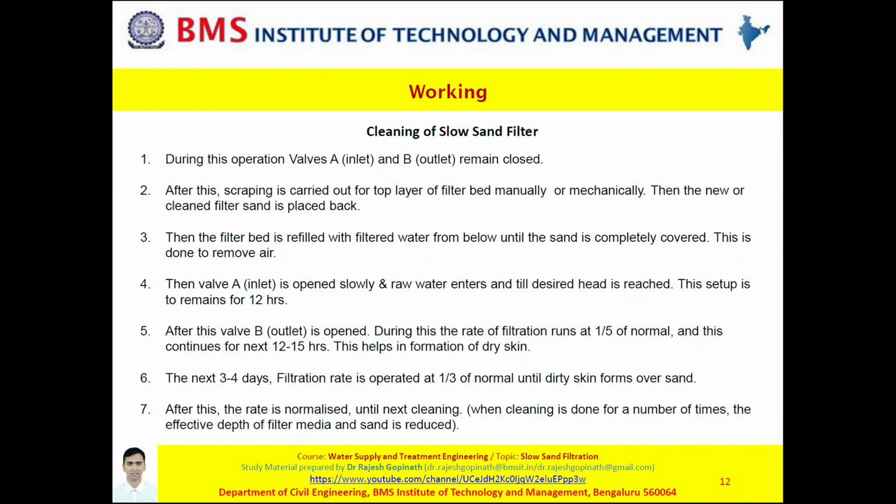As the water passes through sand to gravel into lateral, it goes on filling until it reaches valve B. By doing this, we accomplish the fact that it has completely removed air and that there is no air trapped anywhere in the filter chamber or in the laterals or in the main drain. Once we have achieved a desired head, that is a filter head, you need to close valve A. This setup should remain for the next 12 hours.